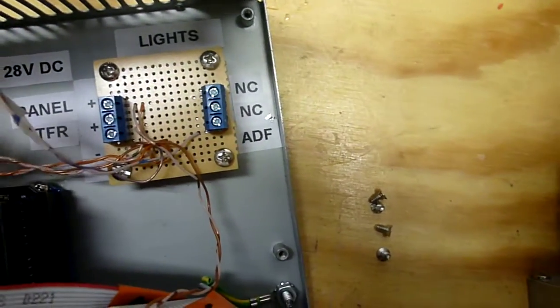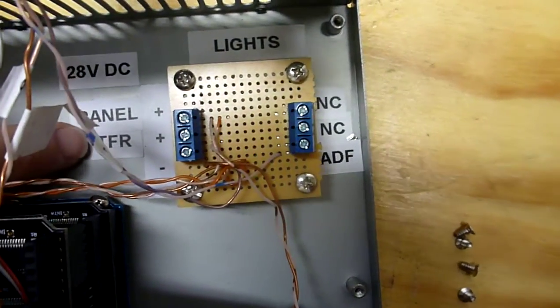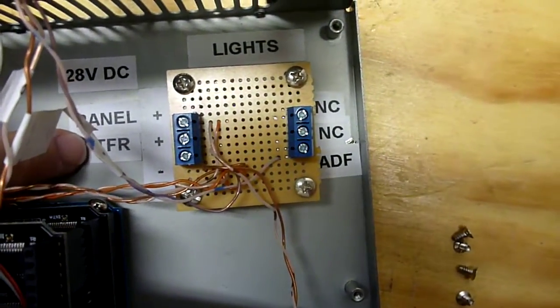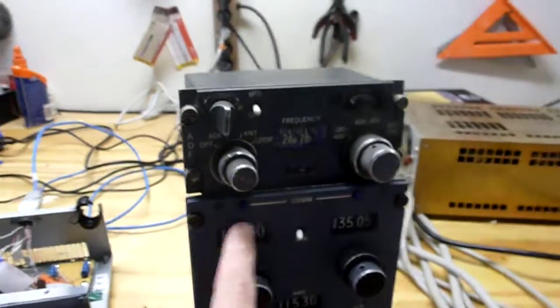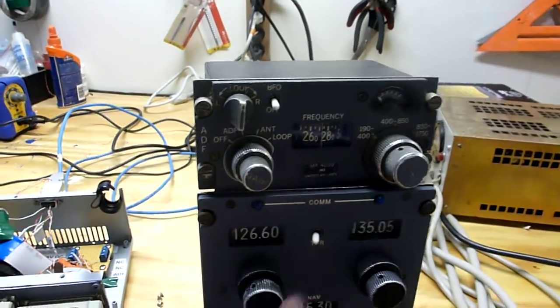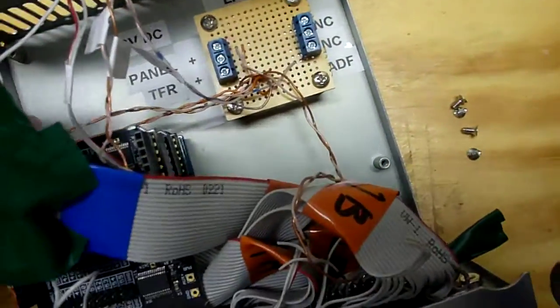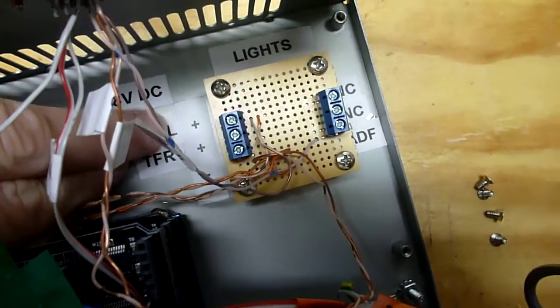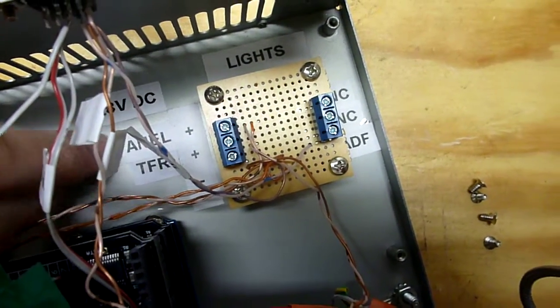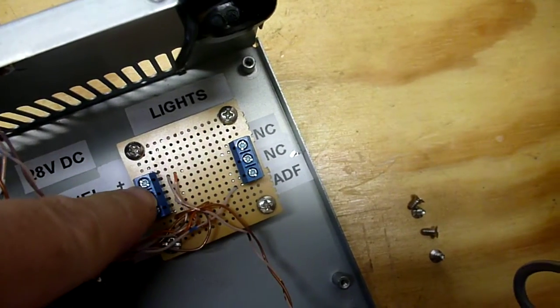This connection here in the bottom left is ground. These other two connections, the TFR is actually 28 volts DC for the transfer light, which is these two little lights here on the com radio. So that needs to always have 28 volts. And then your panel lighting goes on the top left connection here.